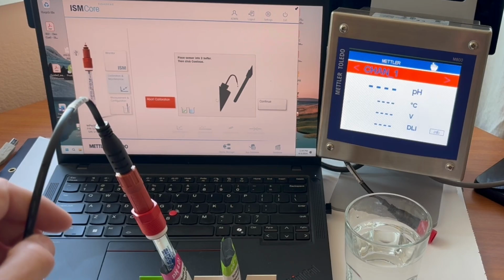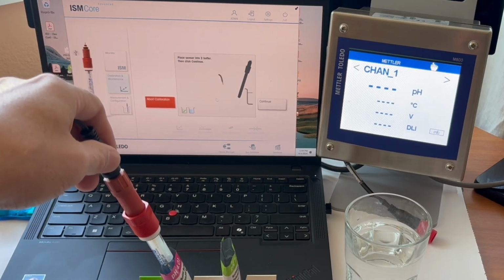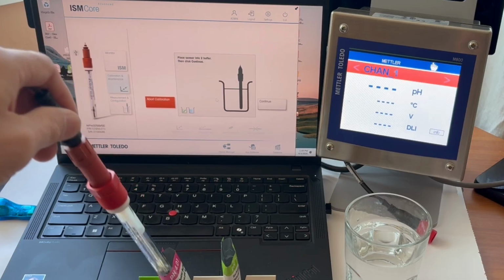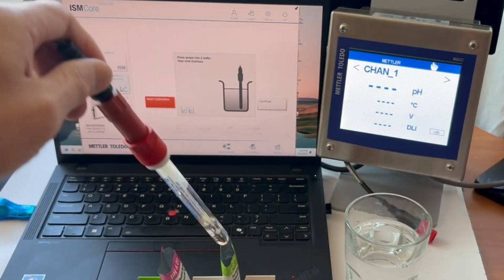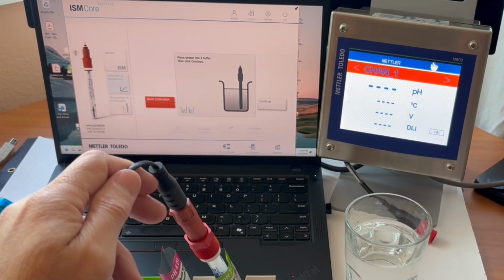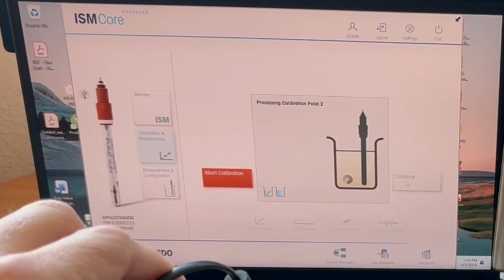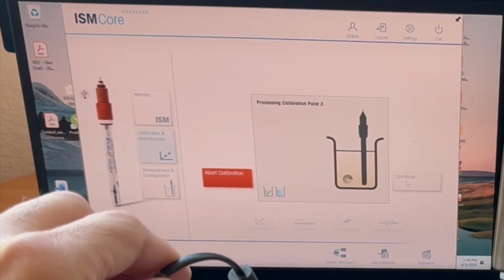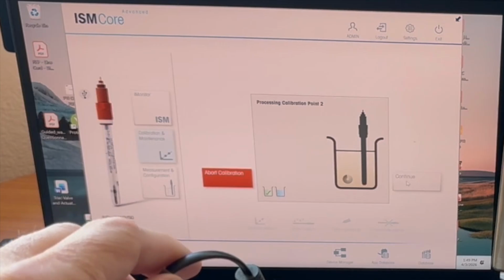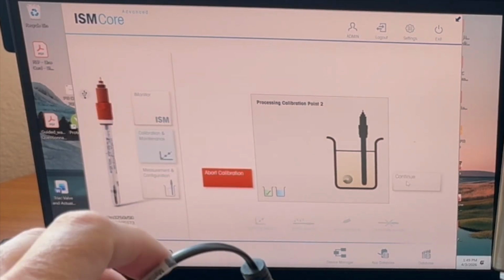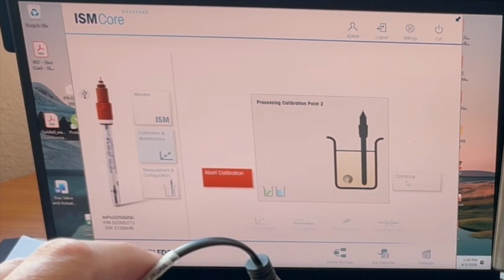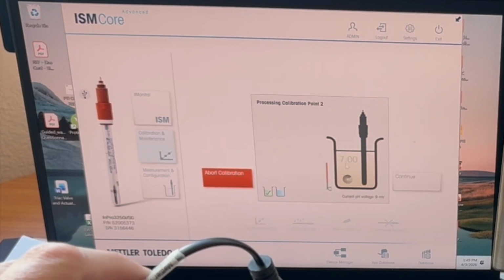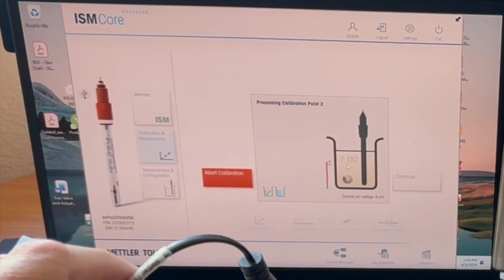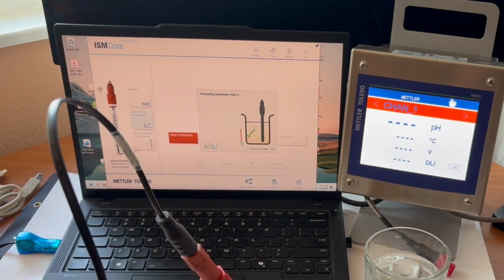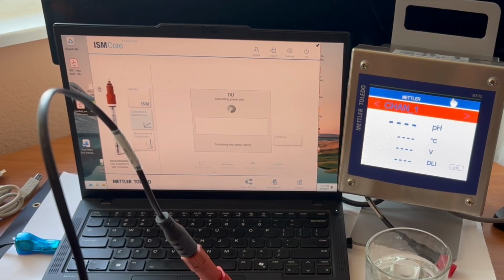And we can see that it passed the first buffer check. All right, it's prompting us, as you can see on the display, put it into buffer 7. Let's do a quick little rinse. Good technique. Drop it into the next buffer, and then it tells me to click continue. It's going to sense the millivolts that it's in, determine what that buffer is, and then present that to us, and then do a stability check before either accepting or not accepting the calibration. So I mean, it's pretty quick to recognize that it's in buffer 7. And we can see it locked in on buffer 7.